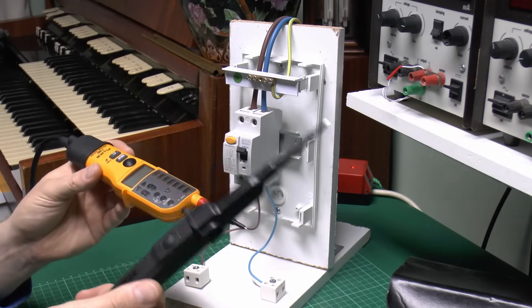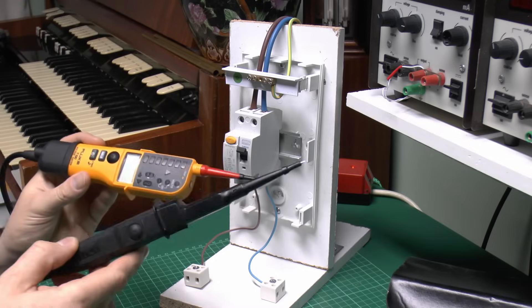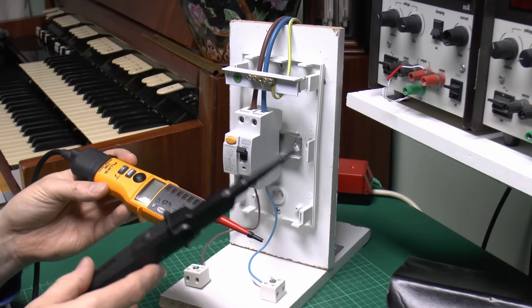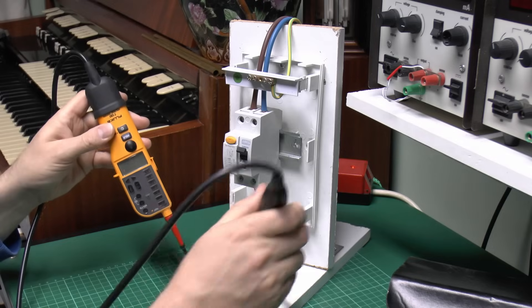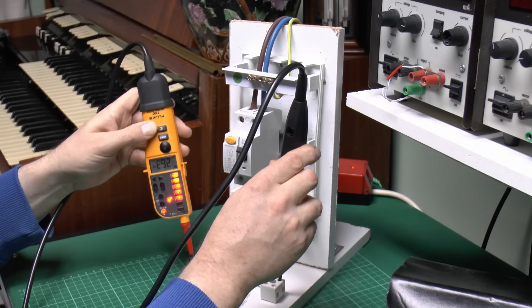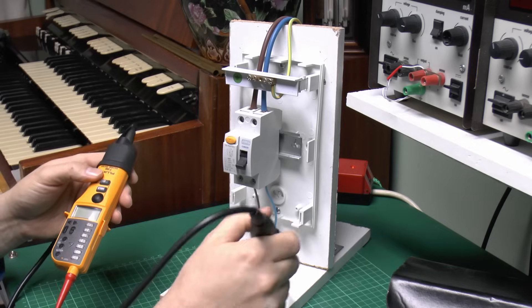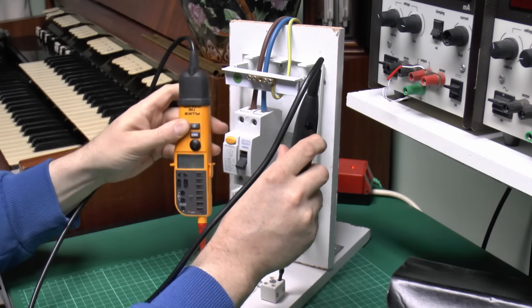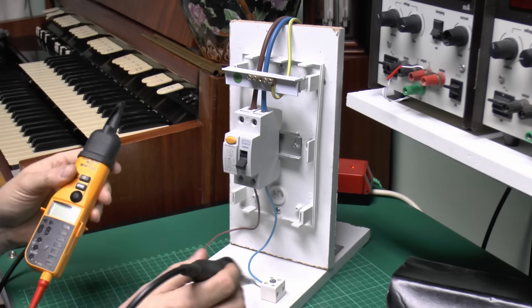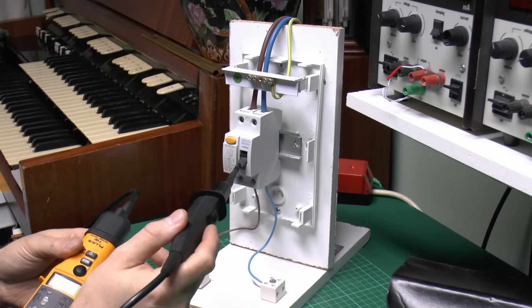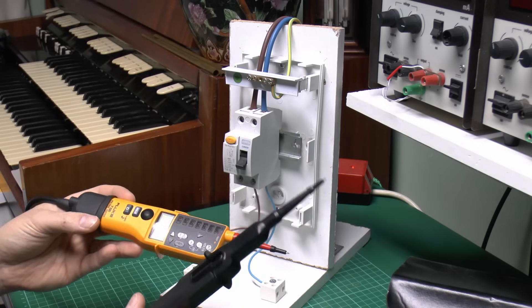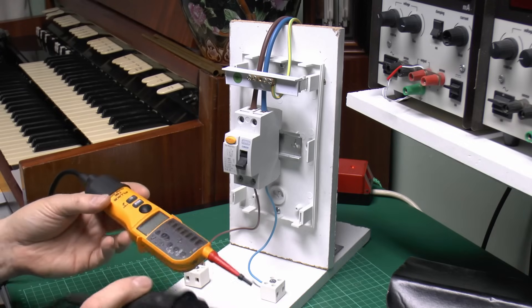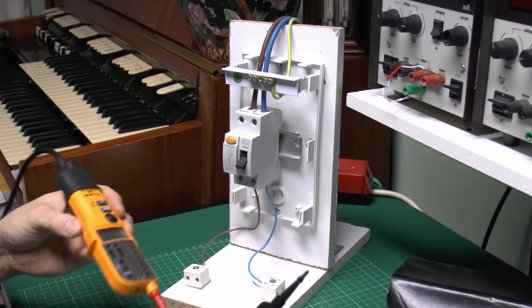Now when it comes to using these in the real world, there's three stages to using these, and the first of those is to make sure that the thing you've got for testing is actually working still. So clearly if there's a break or some malfunction that occurred, totally useless. So of course the first thing to do is confirm that it does actually work, so easily done of course by just connecting it to a power supply there, and actually that illuminates as expected. Now if we switch off here, we should now find that these are disconnected, so again we'll just go in there and test those a second time, and there you go, there's absolutely no indications there whatsoever. So in theory these are now safe to work on because we've switched off here and that has isolated.